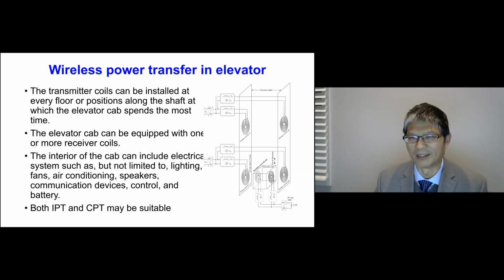When you move the car, the cable runs with the car, and it creates anywhere from 5% to 20% of losses of the system. So it consumes a lot of energy. Secondly, the cable over time will get deteriorated. Then we have to maintain it. We may have to replace the cable. So it's a significant cost and the interruption for the service.